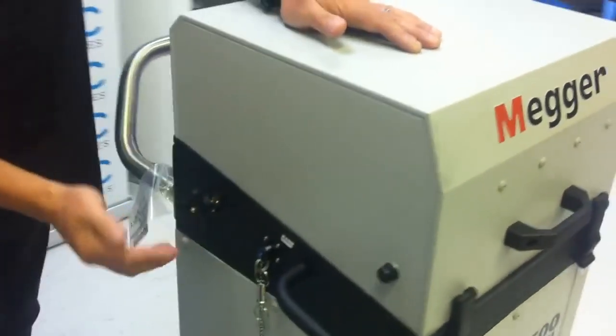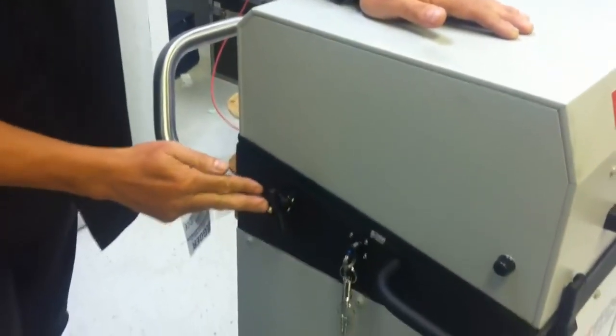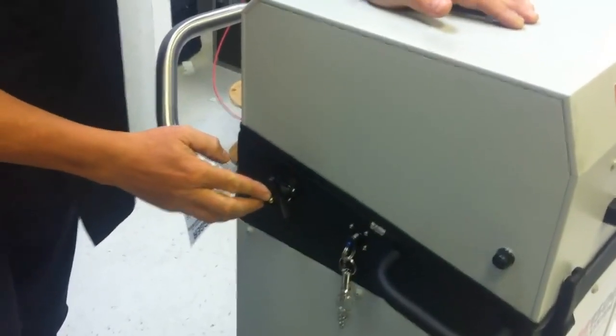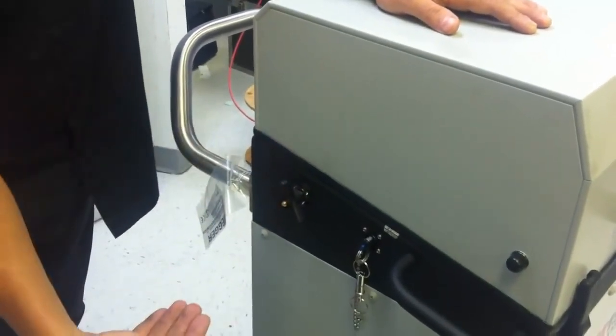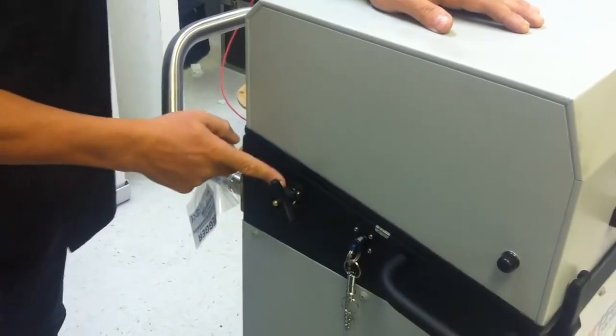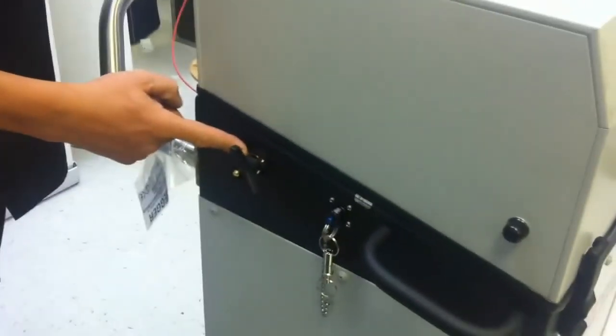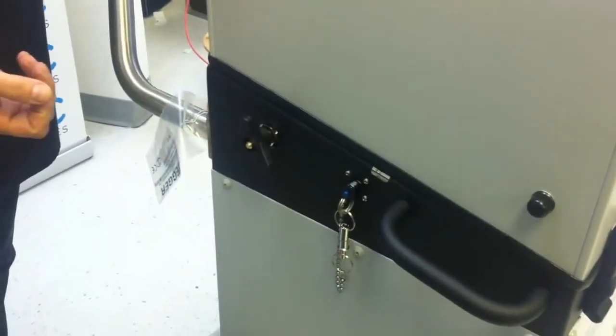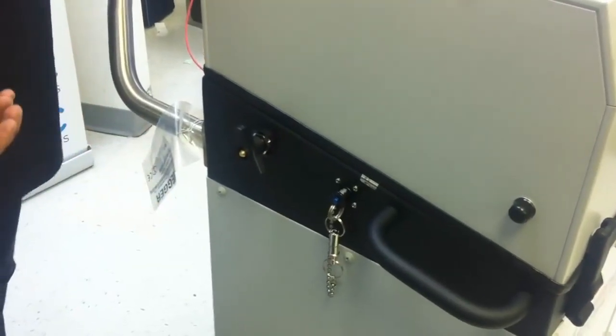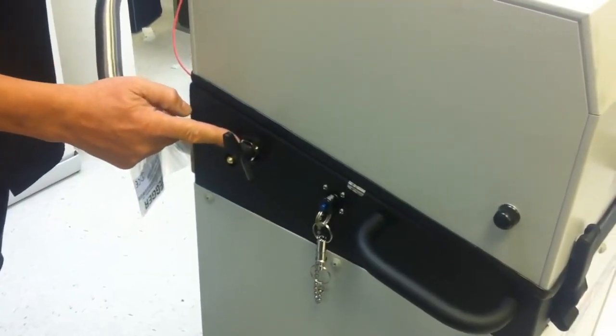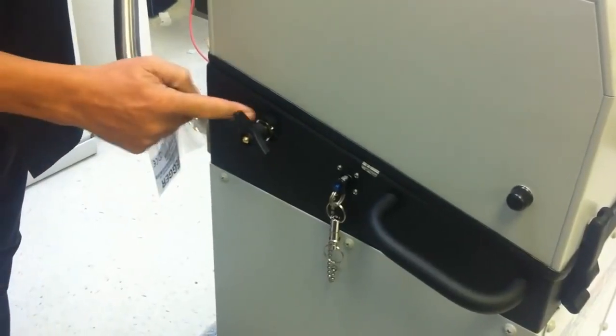Finally, moving to the last side panel, we have our main system earthing. On this connection here, if I'm using the system in the field on the ground, I will run a ground from here to the utility system ground. If I'm running it from the back of a truck, I'll run a ground from here to the chassis of the truck and from here to the utility system ground.